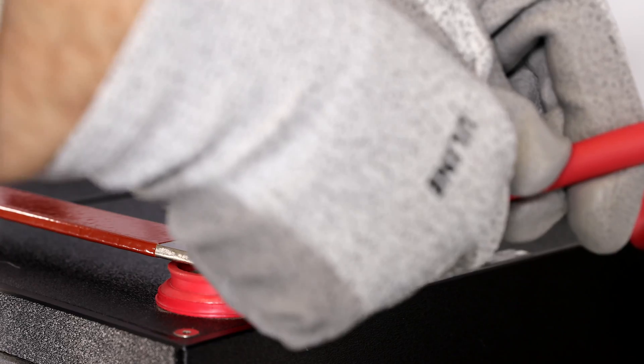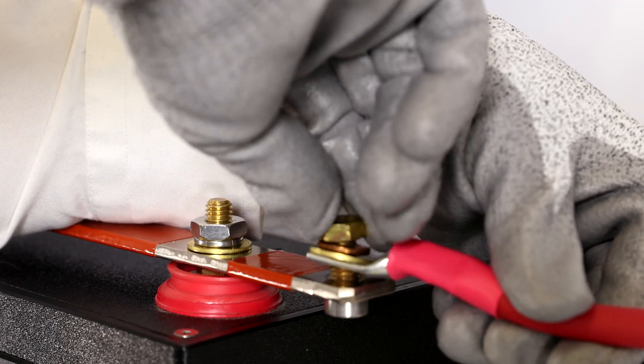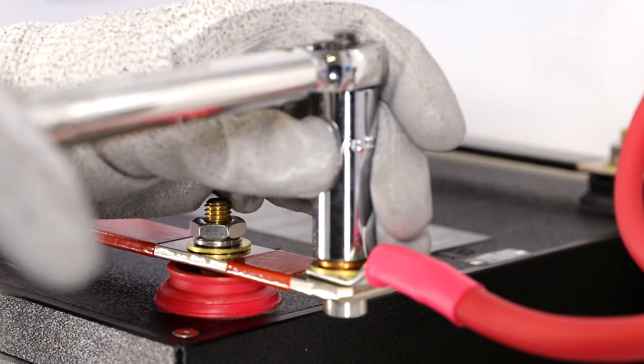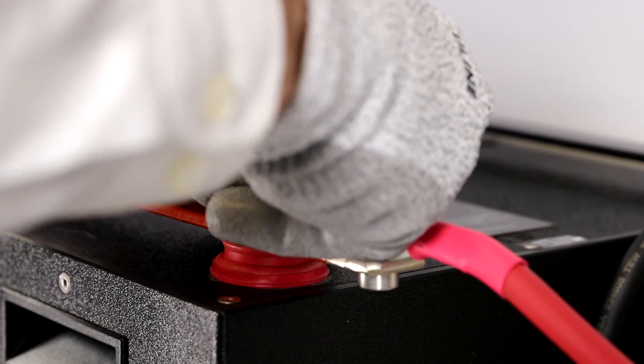Then place the battery's connector. Land the lead's connection lugs onto the battery's terminals. Tighten to 160 inch pounds. Cover the nuts with the provided rubber caps.